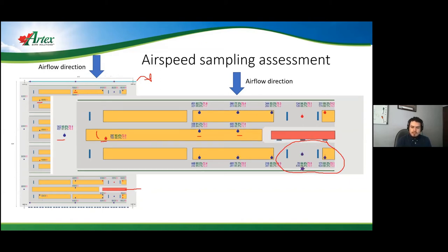Something that was installed when I was there that I thought was very interesting were these three circulation fans. These three 72-inch louvered fans are trying to cool or prevent that dead zone. The idea is that you're going to put these big fans, get the air, and ideally flow across into the other pen. Unfortunately, from both my results and the model, that is not what's happening.